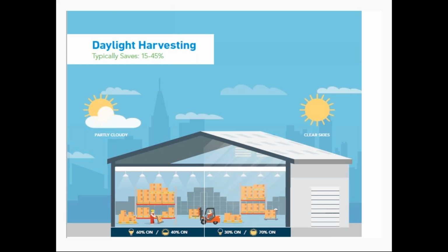Average savings can be anywhere from 15 to 45%, but really it's the power of off that is so attractive about this strategy. There's probably a ton of opportunity where the daylight will actually provide all 30-foot candles in the space, so you could have your electric lighting off. So really, the possibilities are somewhat limitless when you factor in the strategy.